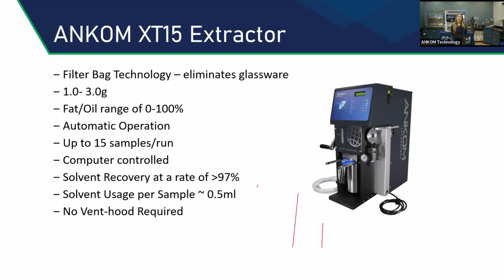This instrument also recovers solvent, which is a huge benefit both from a cost standpoint as well as an environmental standpoint. It has a solvent recovery rate of over 97%, and it reuses the solvent automatically. So you are able to not only recover it, but it will automatically put it in your next run and continue to cycle through until you need to simply pour a little more solvent in to top it off. Because it's a closed system, no vent hood is required.